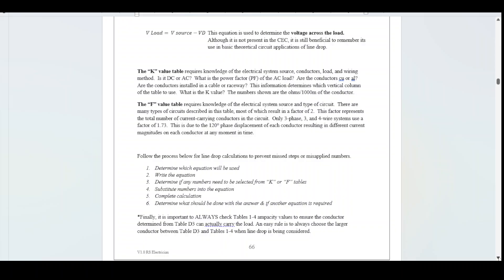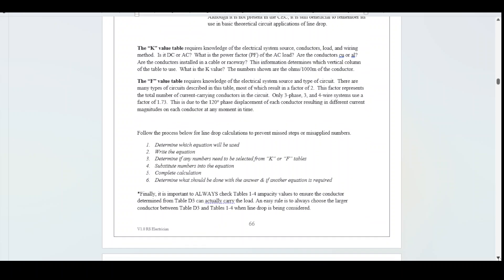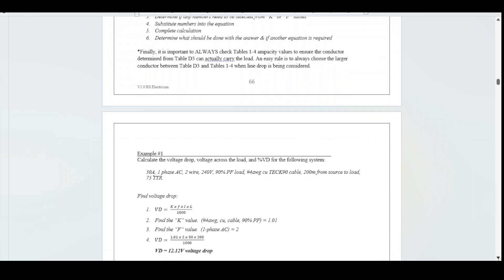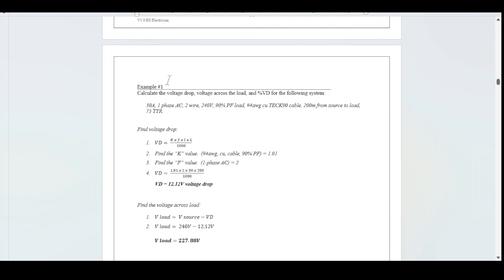Example number 1: calculate the voltage drop, voltage across the load, and the percent voltage drop for the following system. 30 amp, single-phase AC, 2-wire, 240 V, 90% power factor load, number 4 AWG copper, Teck 90 cable, 200 meters from source to load, and 75-degree termination temperatures. Three separate calculations are required: voltage drop, voltage across the load, and percent voltage drop.